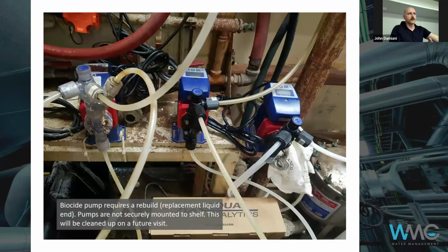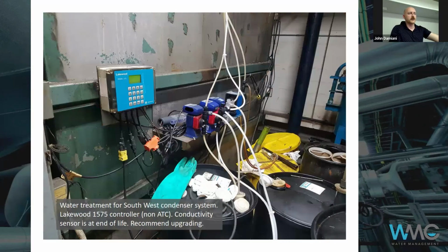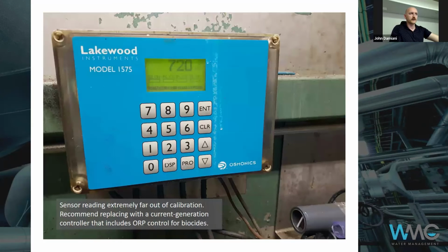These types of things need to be addressed. Fortunately, this here is actually not a food and bev plant, but it's really just to establish the condition we found the system in, and to give as close of an opinion as possible based on the information we have. As you can see, the controller set point in this case is lower than it should be, so it's undercycled, meaning it's wasting water and energy.